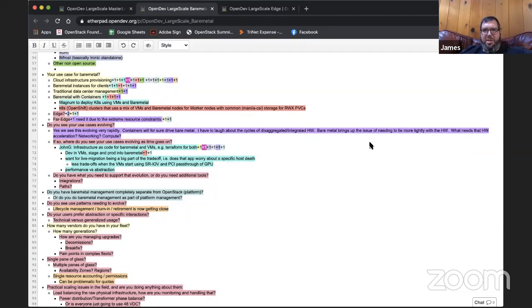So something that we're looking towards is really covering the cradle to grave life cycle for all of our hardware, everything from when it comes into the data center, and we actually talked a little bit about that wired up and walk away. But other things that are really interesting to me are once we reach our projected end of life point for a hardware platform, usually our models show that about 3 to 5 years is about when it's time to start to retire a machine. That has to do with ongoing maintenance costs starting to ramp up after a point, as well as, in some cases with bare metal, the power consumption of that node being so much higher than newer machines coming out for a comparable performance point that it actually makes sense to get rid of the old hardware, resell it, and go buy something new.